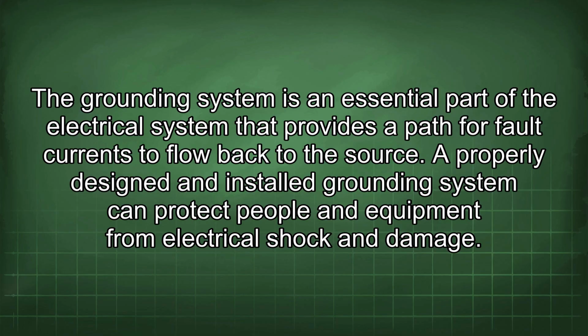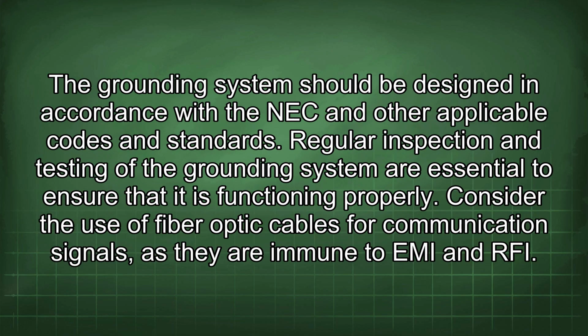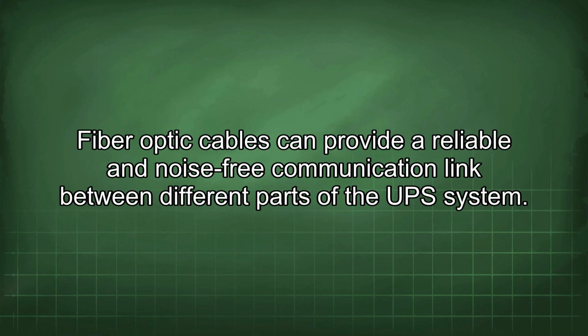The grounding system is an essential part of the electrical system that provides a path for fault currents to flow back to the source. A properly designed and installed grounding system can protect people and equipment from electrical shock and damage. The grounding system should be designed in accordance with the NEC and other applicable codes and standards. Regular inspection and testing of the grounding system are essential to ensure that it is functioning properly. Consider the use of fiber optic cables for communication signals, as they are immune to EMI and RFI. Fiber optic cables can provide a reliable and noise-free communication link between different parts of the UPS system.